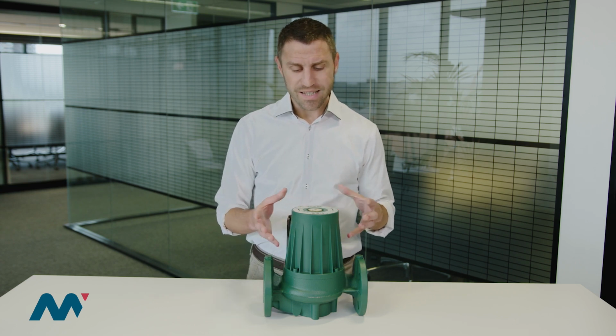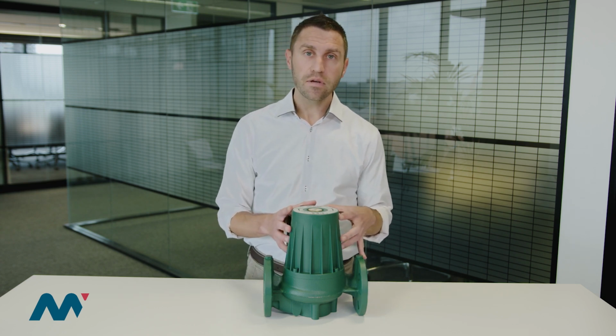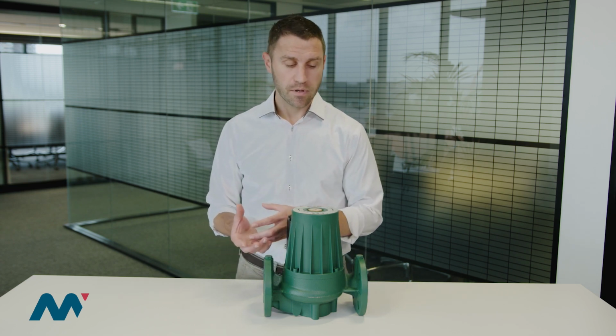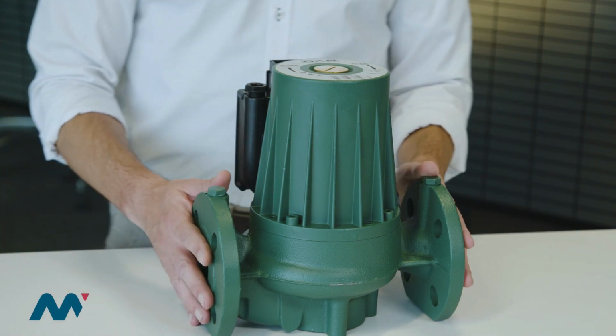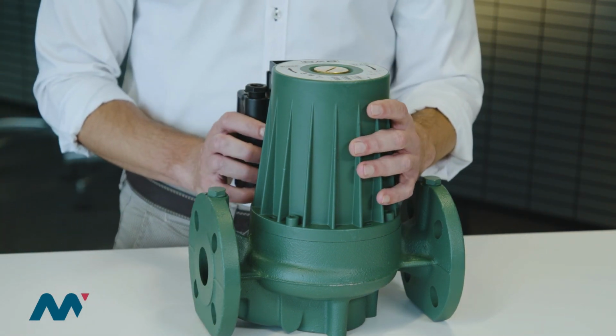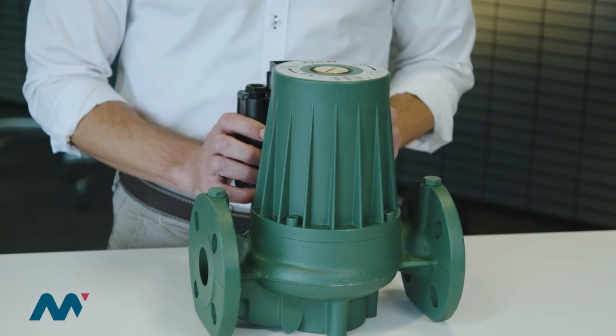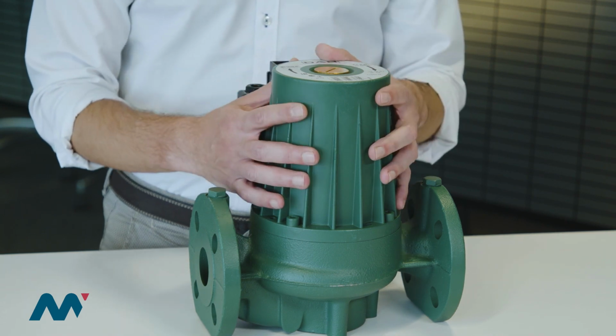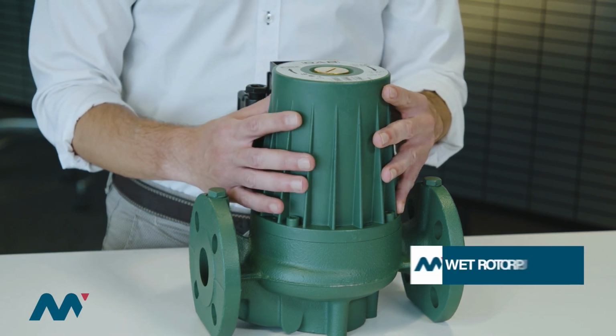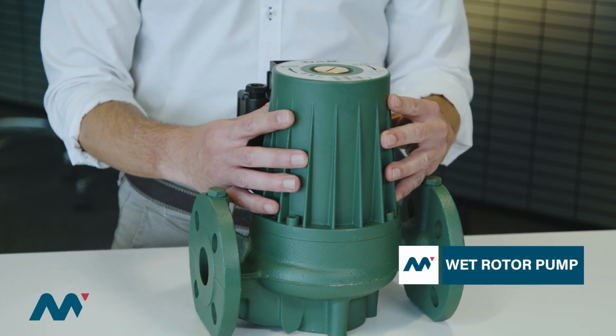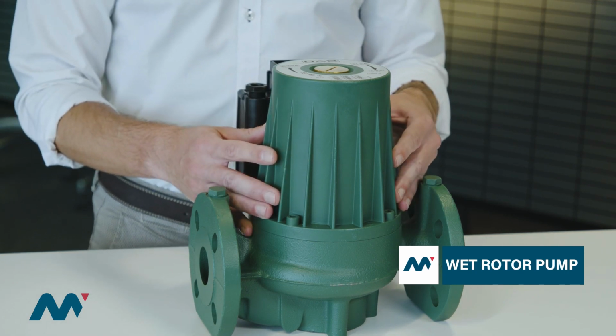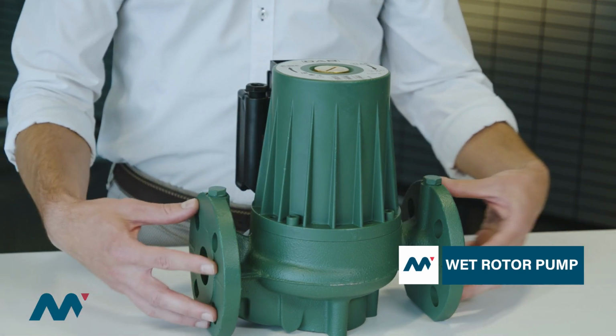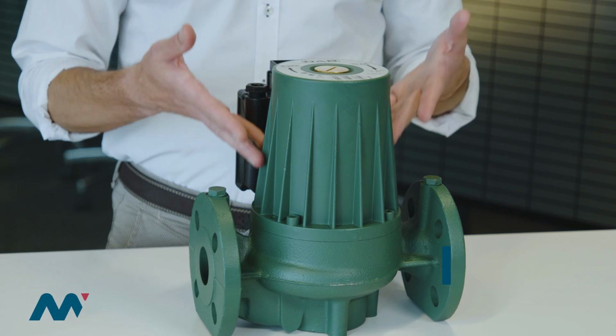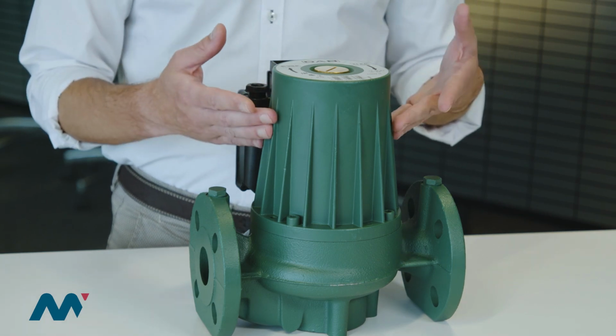So what is different in a circulator compared to another pump? We said about suction and delivery, but the technology inside the pump is also different. Usually circulators are wet rotor pumps. That means there is no mechanical seal. The water that passes through the wet end goes into the motor to cool it down.